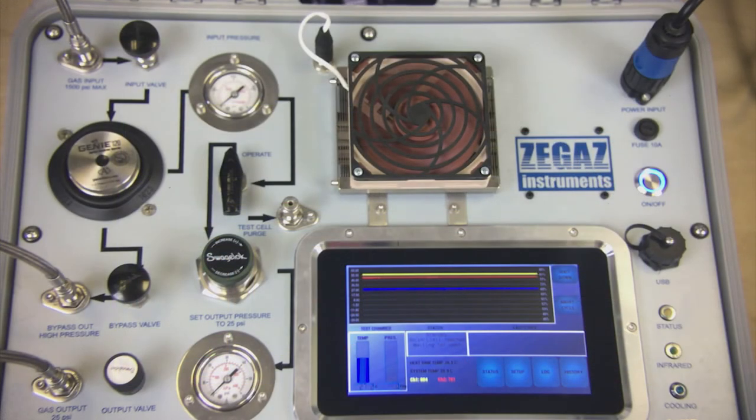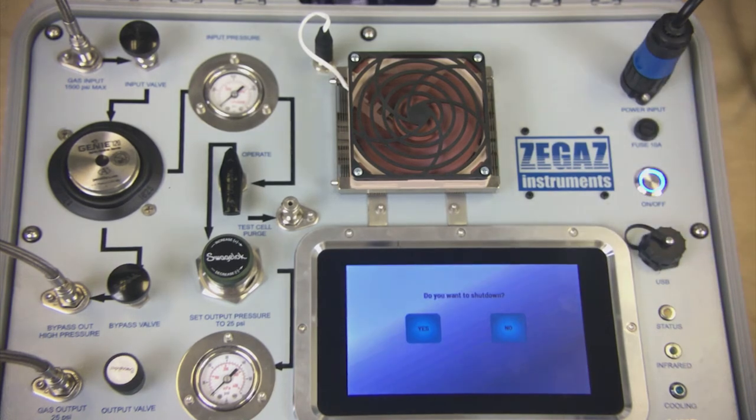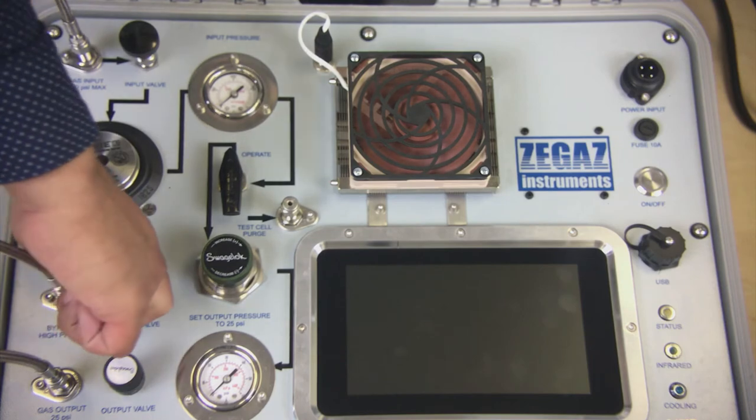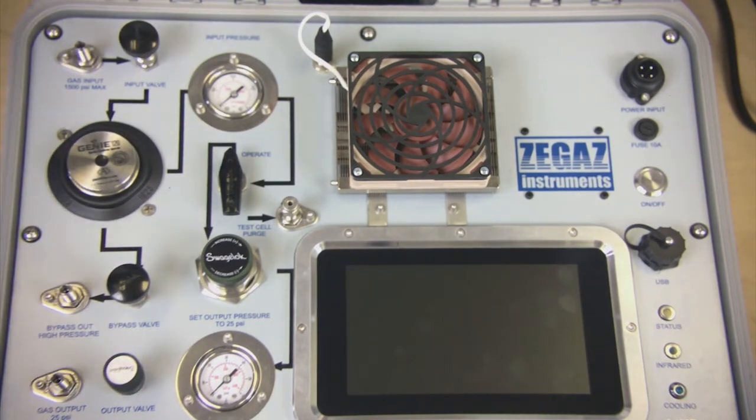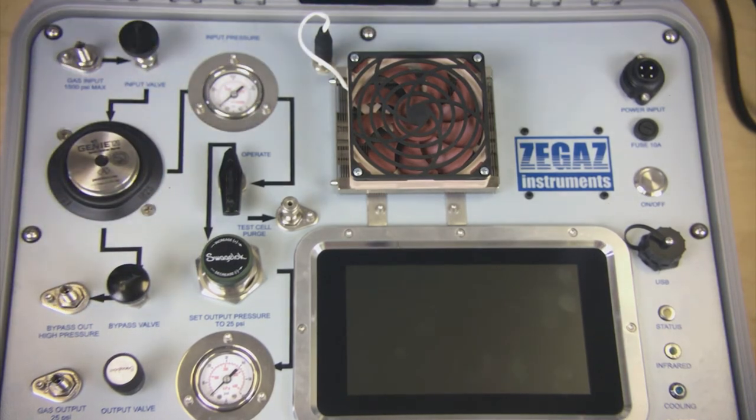Once the measurements have been completed and you are ready to power down the unit, press the shutdown button and press yes when prompted. Turn off power when the screen goes blank and disconnect power from the unit. Relieve pressure by opening up the bypass valve for a few seconds. Close all the valves completely and disconnect your gas lines. Ensure the system has been depressurized by opening up the bypass valve momentarily to relieve any residual pressure. Close all the valves and close the unit and move on to the next test location.